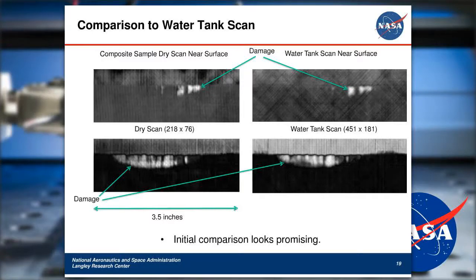Okay, so with those results that we had previously, we wanted to compare a C-scan from a dry scan to a water tank scan. If you look at the images shown on the right-hand side, the two images on the right-hand side are the water tank scan. That is kind of like the gold standard of ultrasonic inspection. That was done with a higher resolution, about 451 by 181 pixels. This is using a focused transducer, I think about 10 megahertz, so it's focused on the surface. So that is our water tank scan.